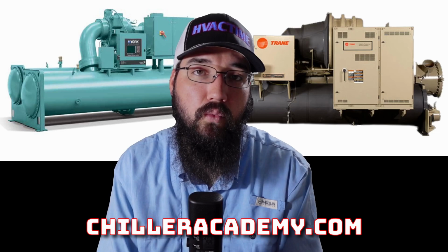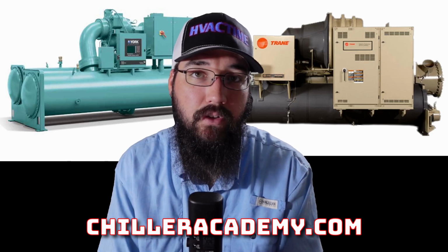514, which was, well, that's the new one. So there's two new ones on the low pressure side. 514 is one of them. Technically, 123 replaced R11, and now 123 is being phased out by 514 and the next one. So 514 at 45 degrees is negative 8.5 PSIG, and 1233ZD. Technically there's an E in there, but anyway, to summarize, it is negative 5.2 PSIG at 45 degrees.